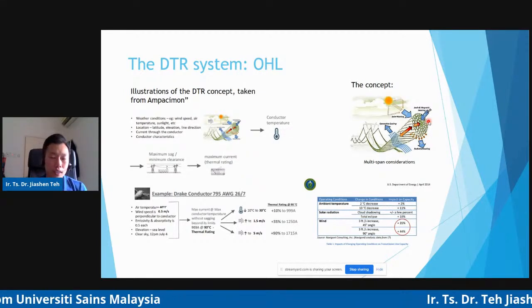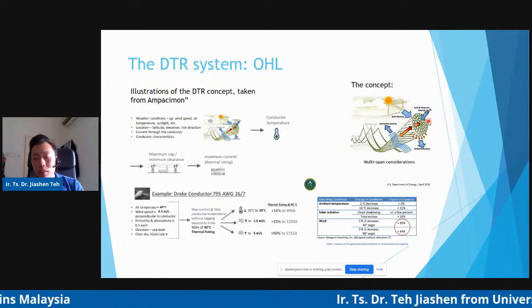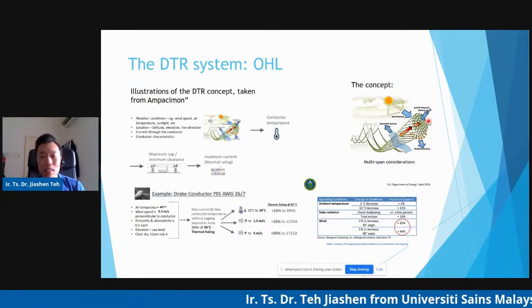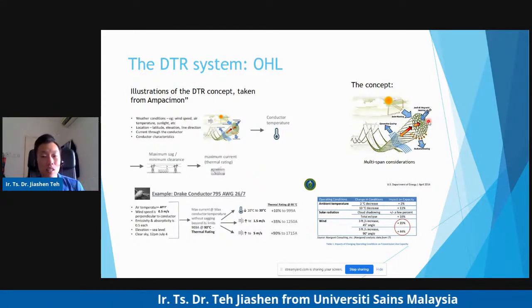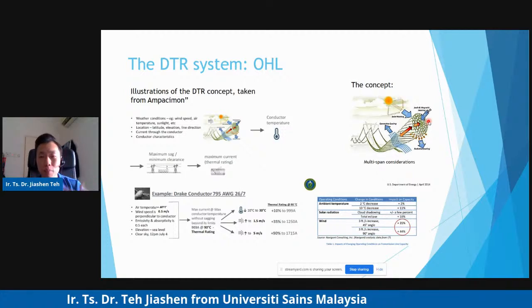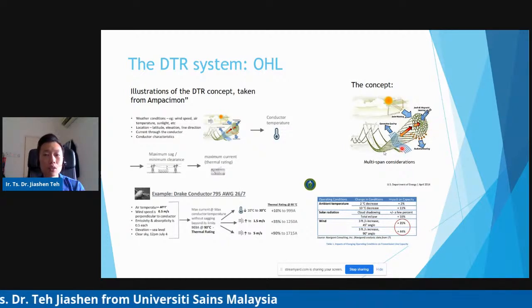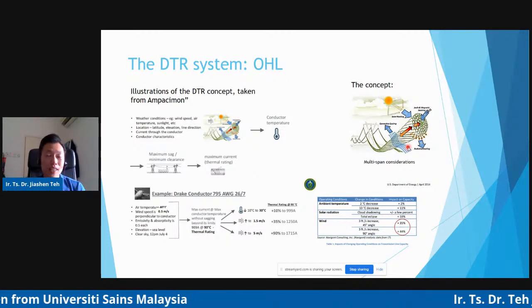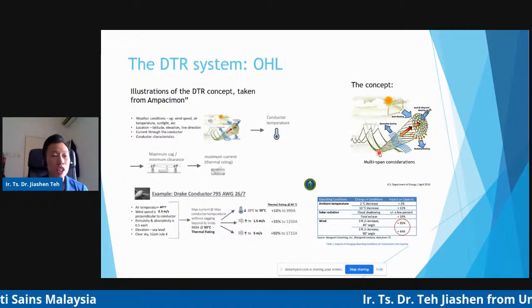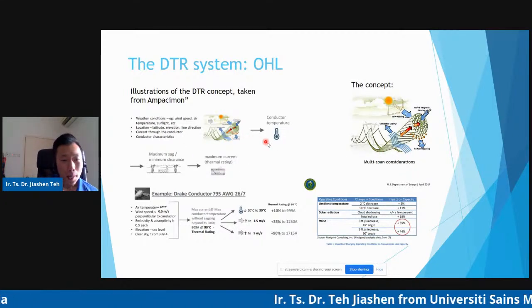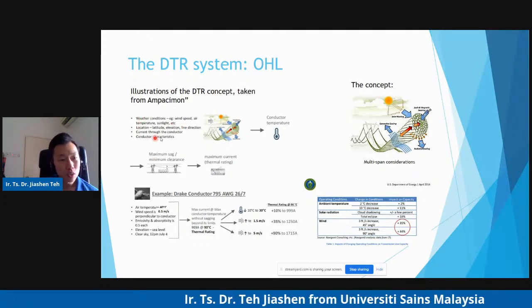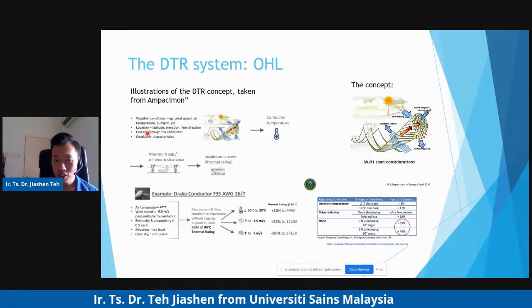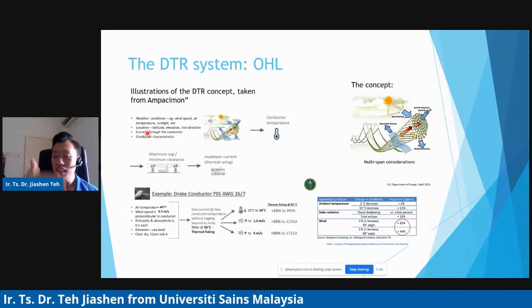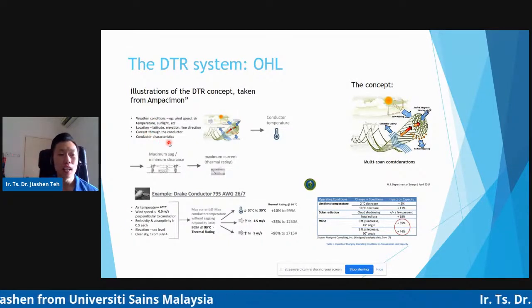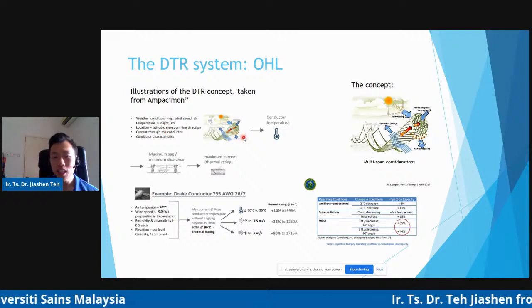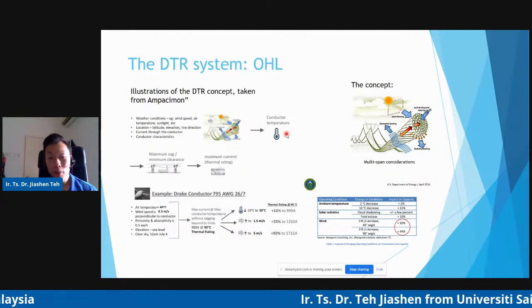All this thermal cooling and heating can be balanced in the equation to calculate the line rating and also the temperature of the conductor, as described in IEEE 738. As we consider all these weather conditions, the location, the latitude, and the elevation of the conductor, we use them to calculate the DTR, and then we can calculate the conductor temperature.